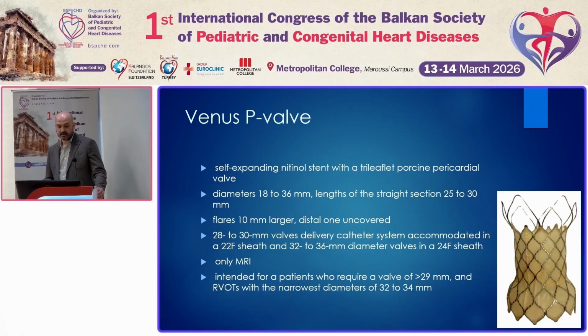The next valve, self-expandable Venus P-valve, a 3-leaflet porcine pericardial valve, diameter 18 to 36, for even bigger RVOTs. So the length of the straight section is 25 to 30. The flares are 10 millimeters larger. Distal is uncovered. That's also important, like I said, to prevent jailing and closing of the branches of the pulmonary artery. So 28 to 30 millimeters is delivered with a 22 French sheath, and 32 to 36 with a 24 French sheath.